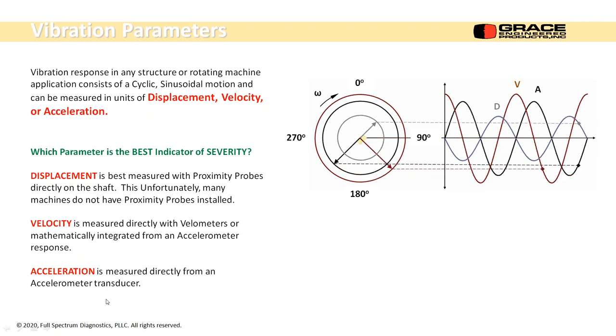Acceleration is measured directly from an accelerometer transducer. There are a few good reasons to use acceleration, one of which is high speed gearboxes. Centrifugal compressors have lots of teeth on their high speed shafts, and you can get really high gear mesh frequency. That's one of the limitations of velocity: you don't see those gear mesh frequencies nearly as well. And manufacturers usually quote their alarm levels in acceleration.